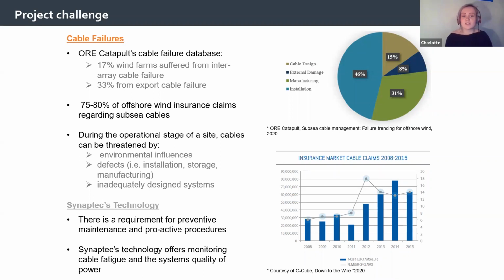The possibility of more incidents occurring or having happened but being unreported is very possible, as there is limited access to cable failure data. Although subsea cables make up a very small percentage of the cost of installation, they make up a very high percentage of offshore wind insurance claims. The graph on the bottom right of your screen is from a report produced by the insurance company G-Cube. It shows insurance claims only up to 2015, but it demonstrates the increase there has been in claims and the increase in costs. As more offshore wind farms are installed around the world, there has been an increase in the number of insurance claims. This is costing the industry.